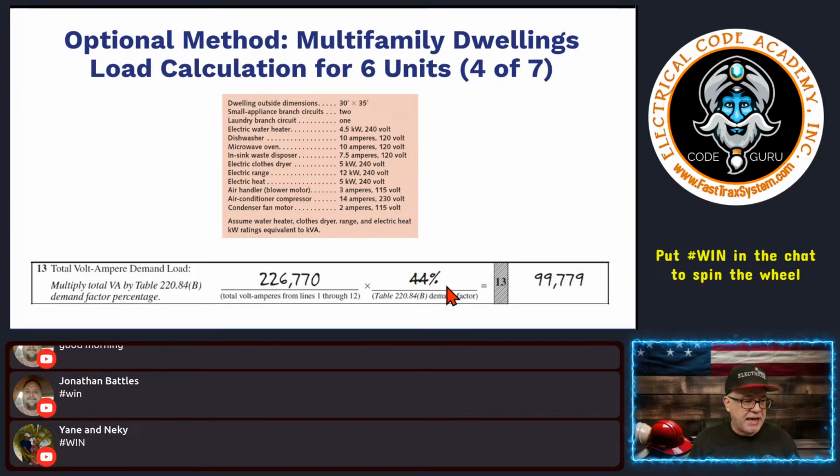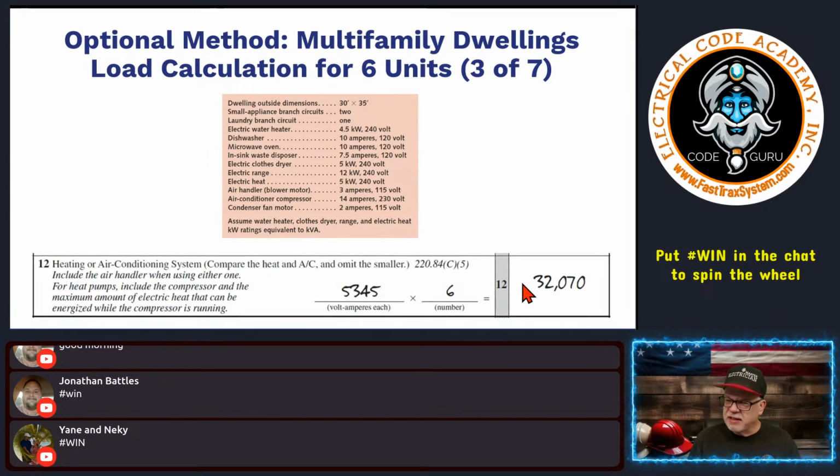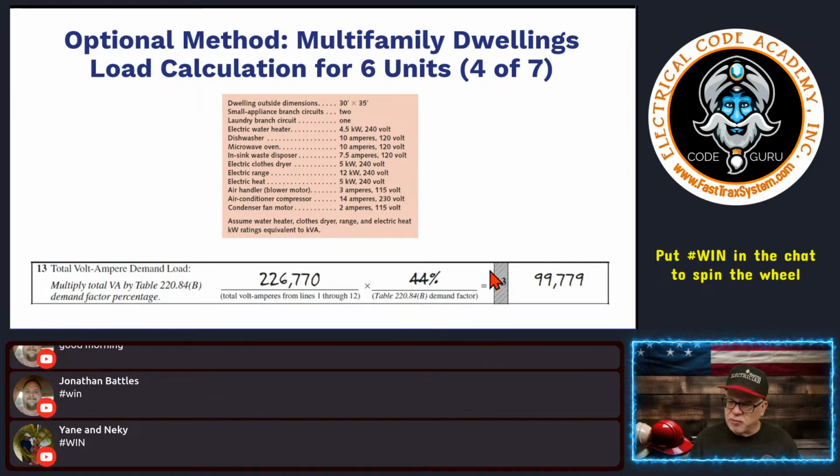We're rounding 0.8, because what does it say we can do in 220.5? We're rounding up. So there we go. At this point, we could wait to the end and do it in the amps, or this is volt-amps, we could do it right here. Typically, I wait until the end, but we're okay. We can round it here. It's going to ultimately work out the same way anyway, so it really doesn't matter. So that's our number.